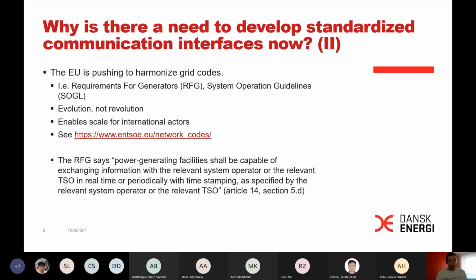I've taken a quote regarding this exchange of information between the producers and their network operator. It says no more and no less information should be exchanged, and the TSO will define which information will be in real time. In Denmark, this has resulted in an expectation that in the coming years, every production unit above 1.5 megawatts will have real-time online measurements sent to their local distribution operator if they're DSO connected, and then further forwarded on to the TSO.